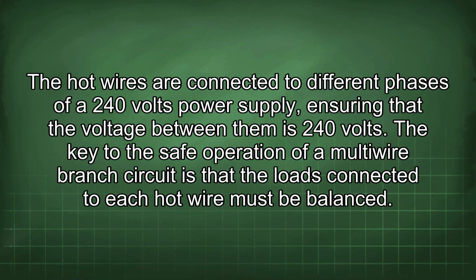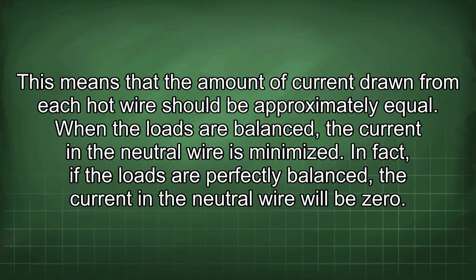The hot wires are connected to different phases of a 240 volts power supply, ensuring that the voltage between them is 240 volts. The key to the safe operation of a multi-wire branch circuit is that the loads connected to each hot wire must be balanced. This means that the amount of current drawn from each hot wire should be approximately equal. When the loads are balanced, the current in the neutral wire is minimized. In fact, if the loads are perfectly balanced, the current in the neutral wire will be zero.